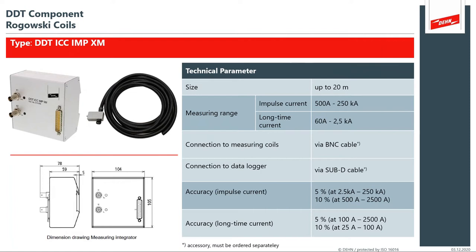We also have what we call the Rogowski coil and the integrator. The integrator basically combines data from the two Rogowski coils — remember, it has a low-amplitude coil and a high-amplitude coil. This gives you a wide bandwidth of measurement. You can actually capture events as low as 60 amps of continuous current and as high as 250 KA of impulse current, truly capturing the scientific waveform as if an oscilloscope were measuring the data. That's a really important aspect of this system.